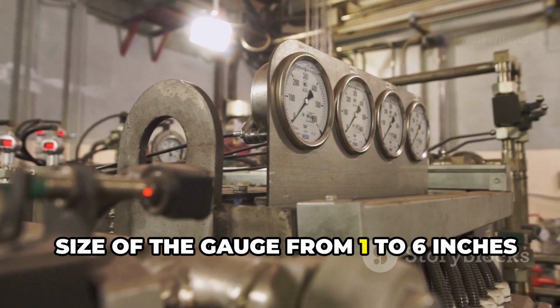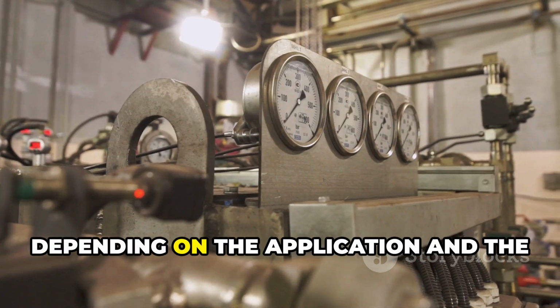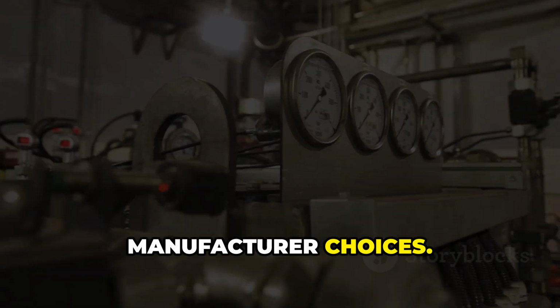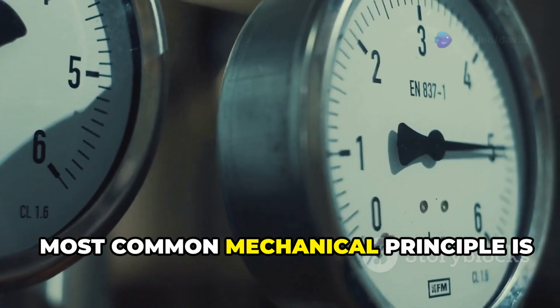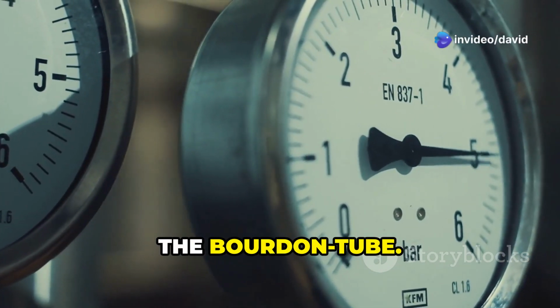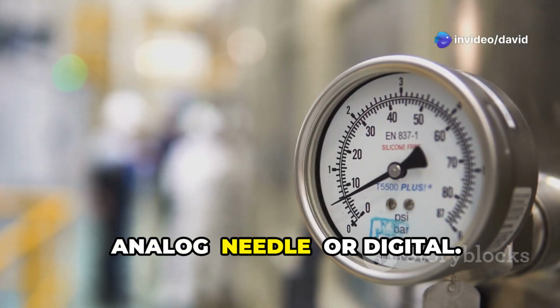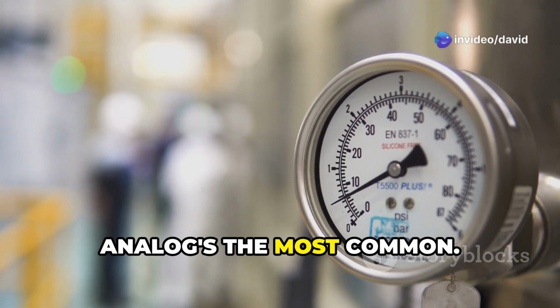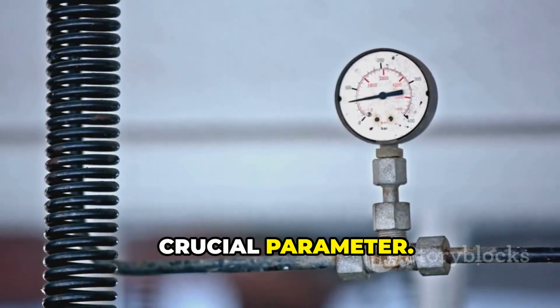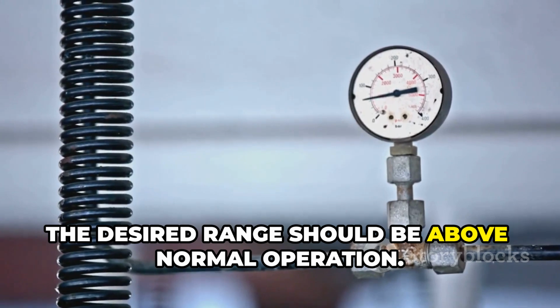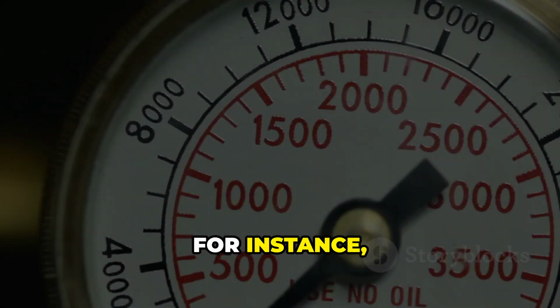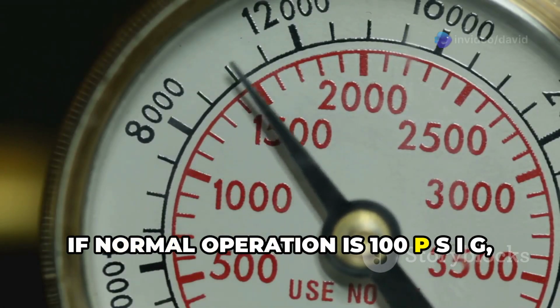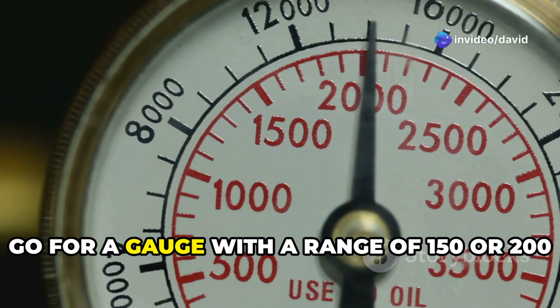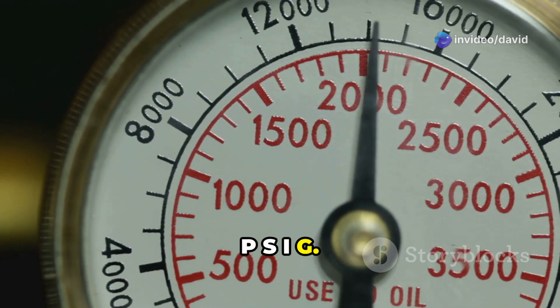Size of the gauge from 1 to 6 inches in diameter depending on the application and the manufacturer choices. Most common mechanical principle is the Bourdon tube. Analog, needle, or digital. Analog's the most common. Crucial parameter: the desired range should be above normal operation. For instance, if normal operation is 100 psig, go for a gauge with a range of 150 or 200 psig.